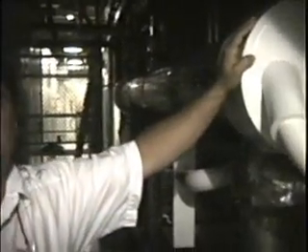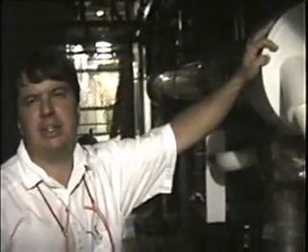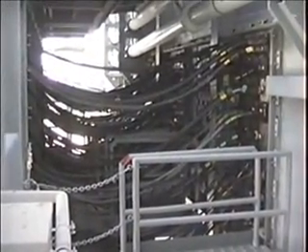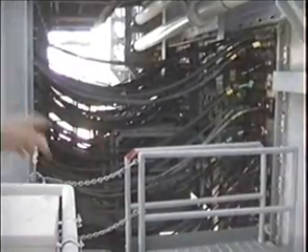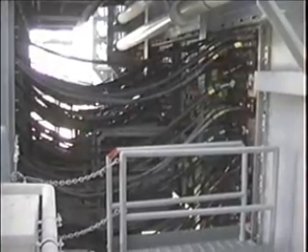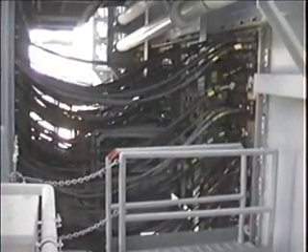This is the chilled water heat exchanger. We're doing ground cooling without the reefer units — we use facility chilled water to cool the orbiter. On launch day we use our refrigeration modules; we use R-22 to get a temperature lower than what facility chilled water can provide. But this is what we use for normal ground cooling ops. Whenever the MLP is brought and parked at the pad, you have to mate all those electrical cables and numerous facility fluid lines every time an MLP rolls up to and departs from a pad — it takes a lot of time.